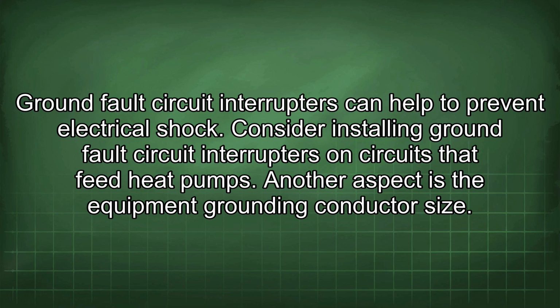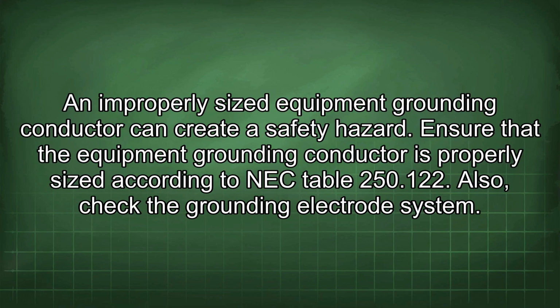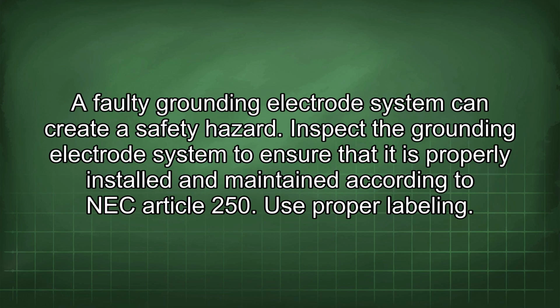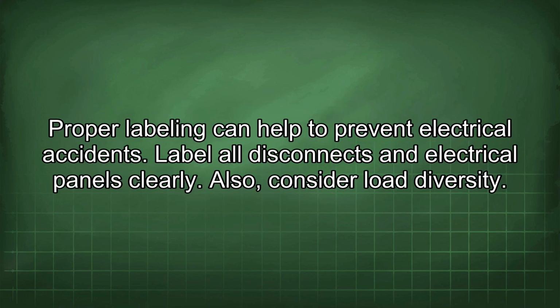Another aspect is the equipment grounding conductor size. An improperly sized equipment grounding conductor can create a safety hazard. Ensure that the equipment grounding conductor is properly sized according to NEC Table 250.122. Also, check the grounding electrode system. A faulty grounding electrode system can create a safety hazard. Inspect the grounding electrode system to ensure that it is properly installed and maintained according to NEC Article 250. Use proper labeling. Proper labeling can help to prevent electrical accidents. Label all disconnects and electrical panels clearly.